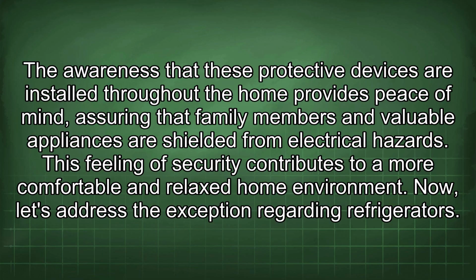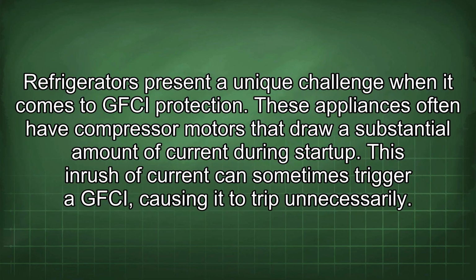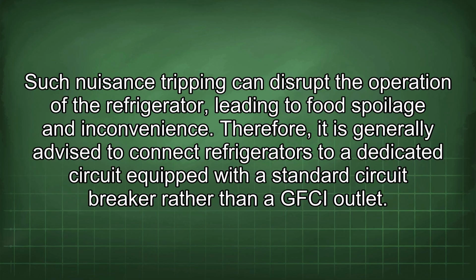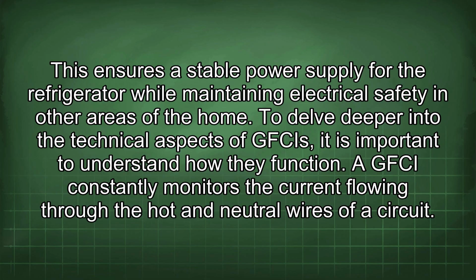Now, let's address the exception regarding refrigerators. Refrigerators present a unique challenge when it comes to GFCI protection. These appliances often have compressor motors that draw a substantial amount of current during startup. This inrush of current can sometimes trigger a GFCI, causing it to trip unnecessarily. Such nuisance tripping can disrupt the operation of the refrigerator, leading to food spoilage and inconvenience. Therefore, it is generally advised to connect refrigerators to a dedicated circuit equipped with a standard circuit breaker rather than a GFCI outlet. This ensures a stable power supply for the refrigerator while maintaining electrical safety in other areas of the home.